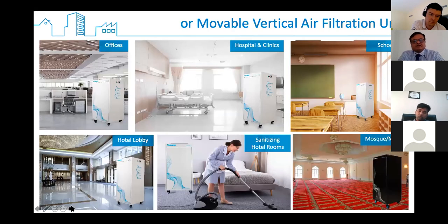Next slide, please. Or a vertical type, which you can use in big offices, let's say, or in hotel rooms when cleaning is happening; this unit can go and sanitize the air. So if you have not put the actual ionization unit and higher UV lamp filtration in every fan coil unit, you can do it when you clean. It takes 40 or 60 minutes depending on how you adjust the UV charge, and you can sanitize the room at that time too. So this is another measure, like in schools, or big mosques and prayer halls, when people come in and go back, you have these movable units. So this locally made solution is also made available by a number of manufacturers.